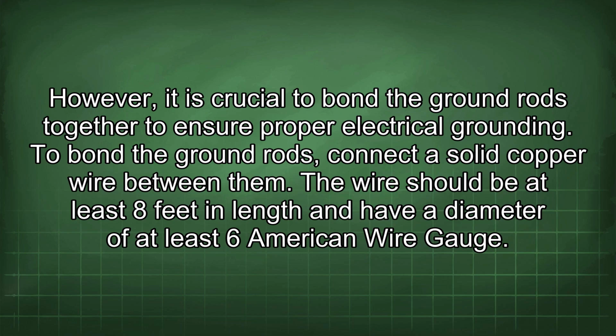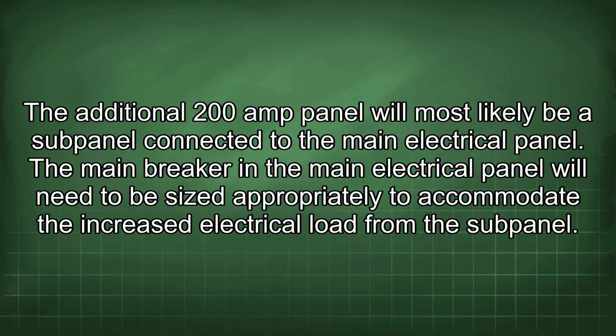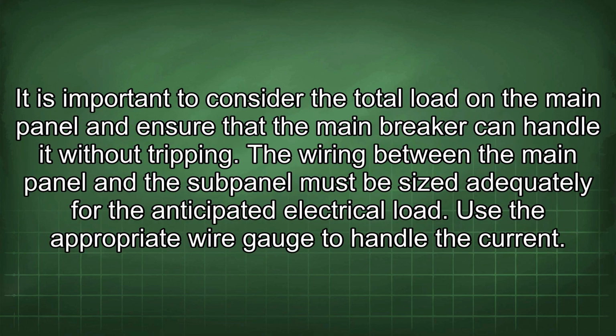To bond the ground rods, connect a solid copper wire between them. The wire should be at least 8 feet in length and have a diameter of at least 6 American wire gauge. The additional 200 amp panel will most likely be a subpanel connected to the main electrical panel. The main breaker in the main electrical panel will need to be sized appropriately to accommodate the increased electrical load from the subpanel. It is important to consider the total load on the main panel and ensure that the main breaker can handle it without tripping.